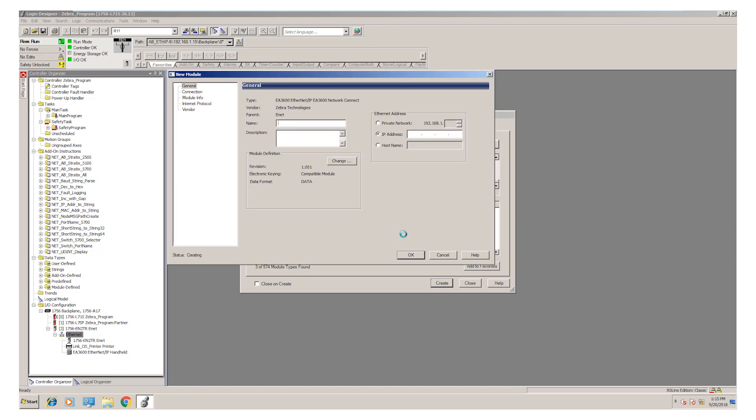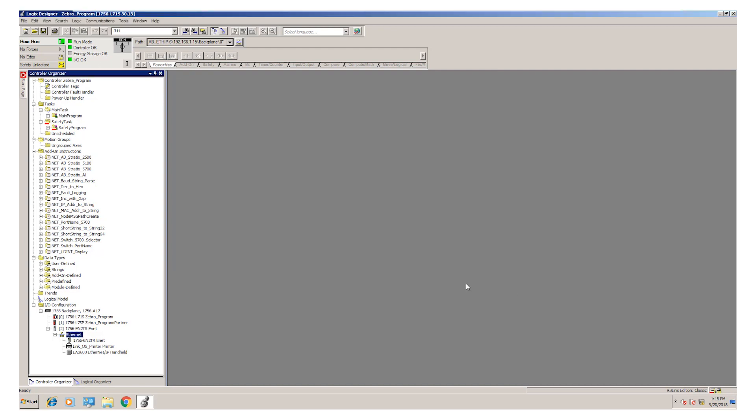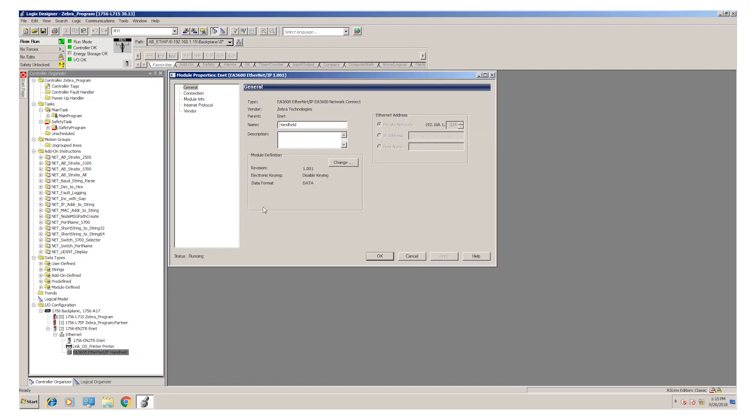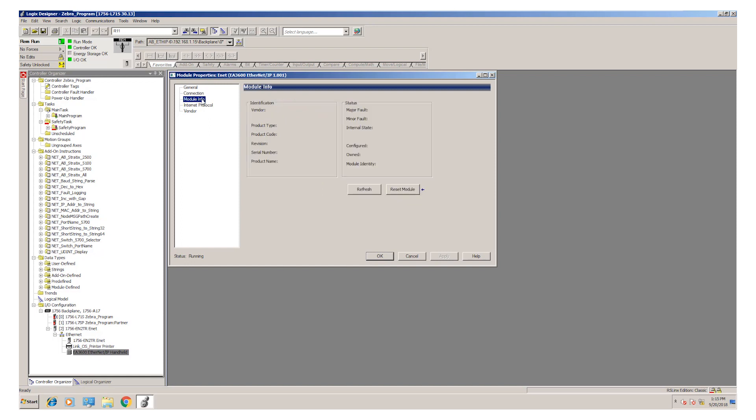At this point, I would type in a name for the device and set the IP address. I've done this ahead of time, so I'm going to cancel this profile and we can look back at the IO configuration tree to see how it's set up. So I double click on the scanner and you can see it's set up as we did earlier. We can set the RPI if we need to, and as you can see it is live.